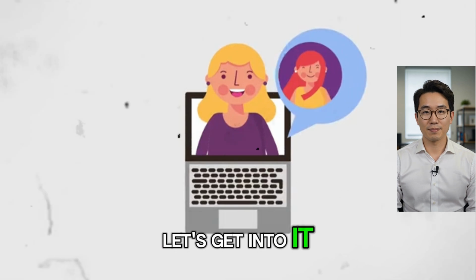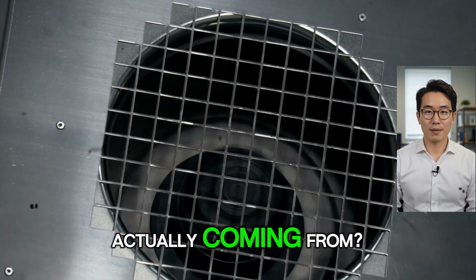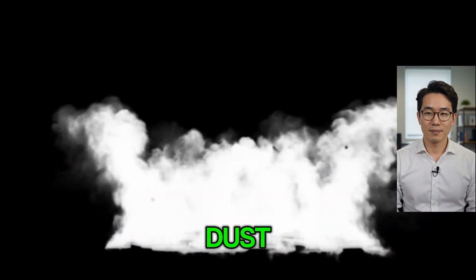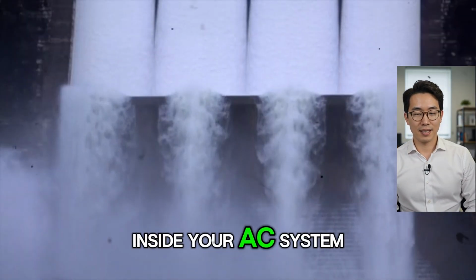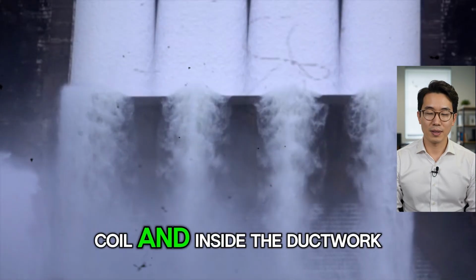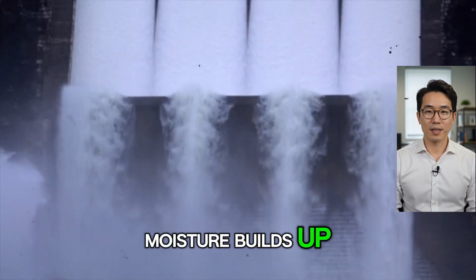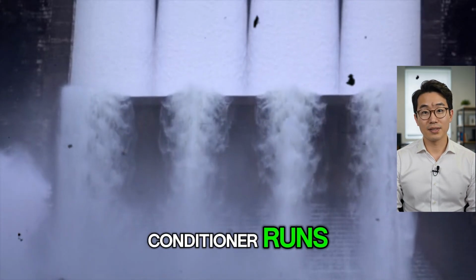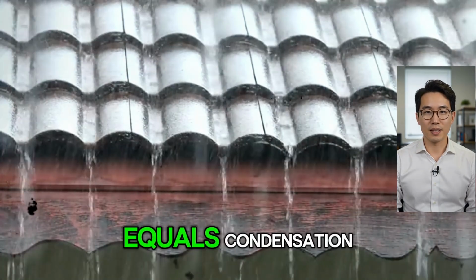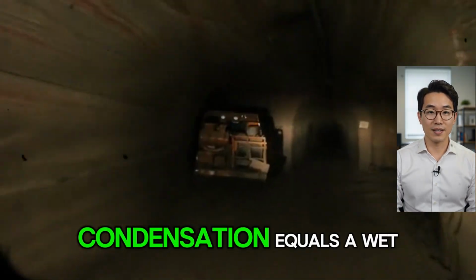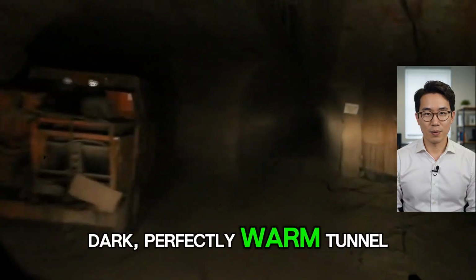Let's get into it. What is that sock smell actually coming from? Here's the thing nobody tells you. That odor is not just dust. That smell is alive. Inside your AC system, especially on the evaporator coil and inside the ductwork, moisture builds up every single time your air conditioner runs. Cool air plus warm air equals condensation. Condensation equals a wet, dark, perfectly warm tunnel.